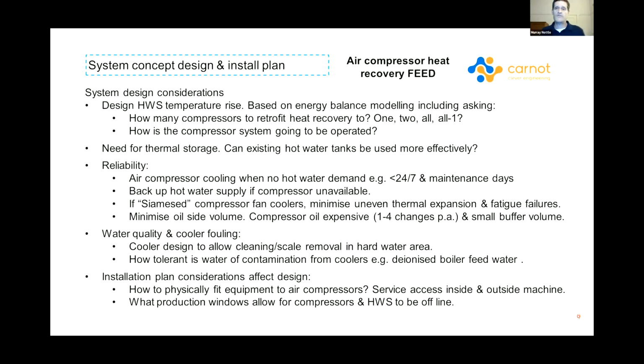So can you physically fit the equipment to the air compressor? You need to get access inside and outside of the machine. Most compressors need access on at least 3 or 4 sides to get to the different filters and coolers and change your oil and check the operation of the machine. And there often isn't a lot of space between the machines to do that. It's typically sometimes as little as a metre, sometimes less, it should be more.